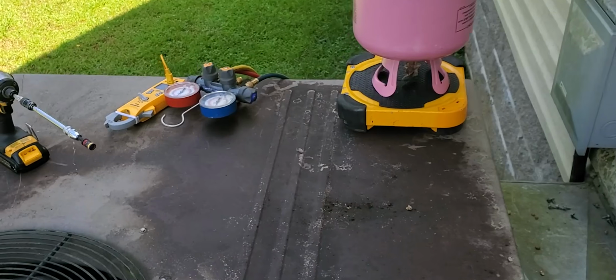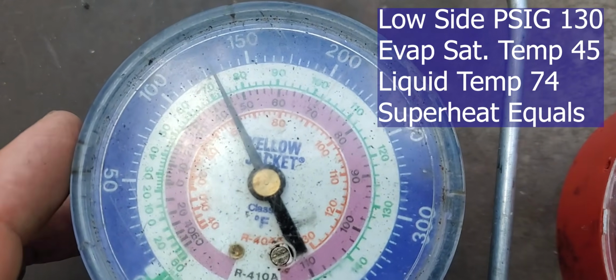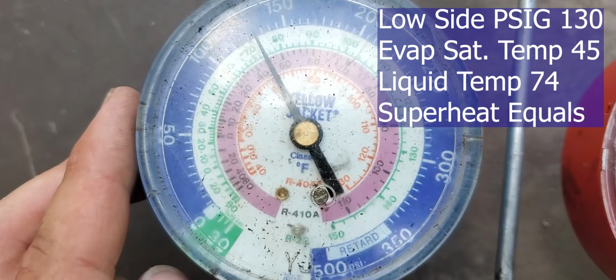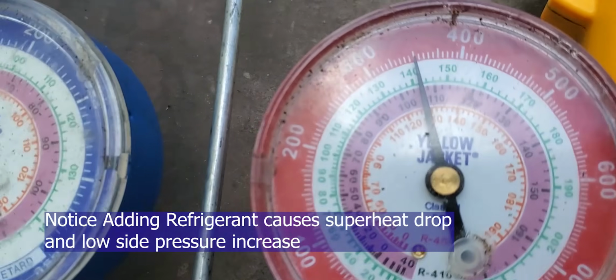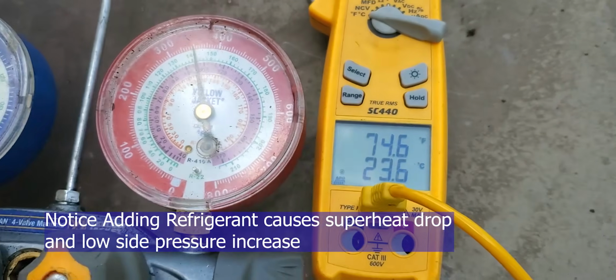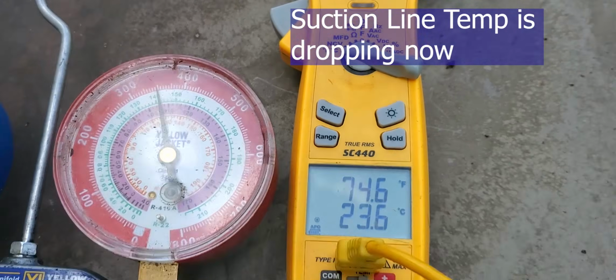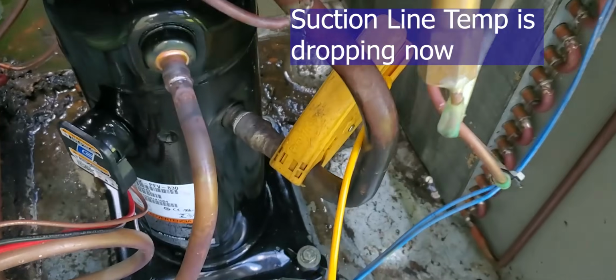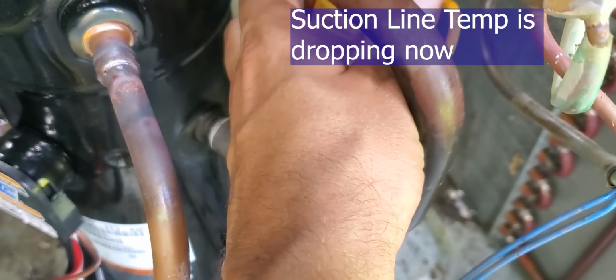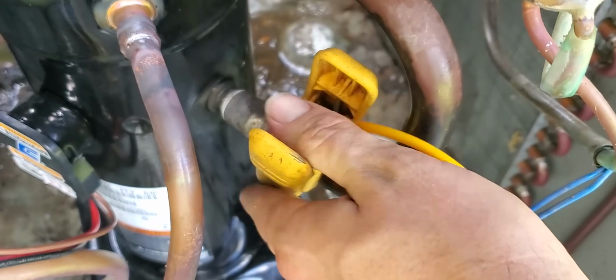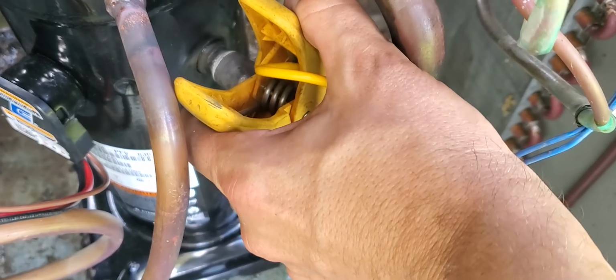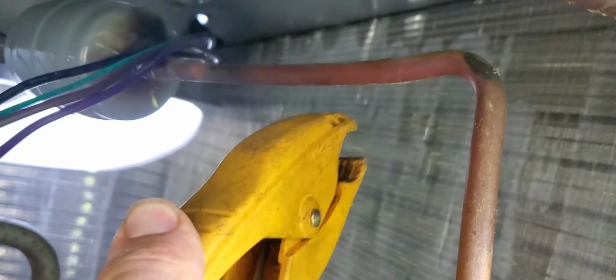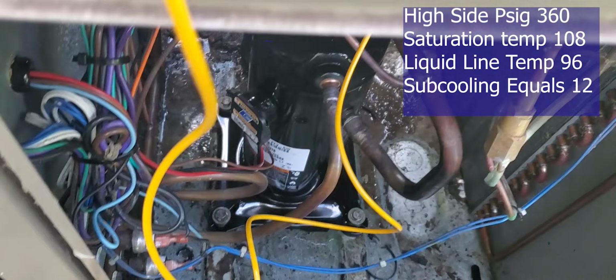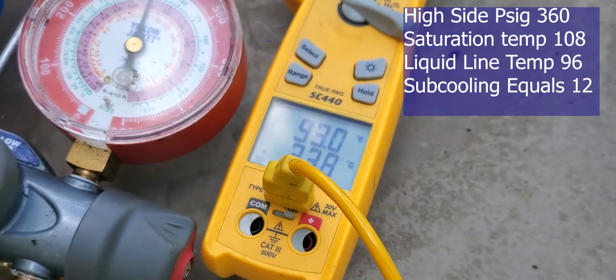So you need scales. Knowing superheat and subcooling is important because it allows you to know whether to add refrigerant or to recover refrigerant. For example, so far we've added refrigerant and our target superheat is between 10 to 15. We've added refrigerant and our suction line temperature has decreased. Our low side pressure has increased. Our superheat was 50 and now it's dropped to 30. So we're getting closer to our evaporator being filled with liquid.